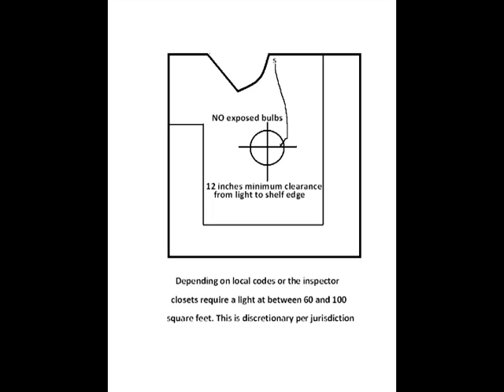Your light source can be no closer than 12 inches from the light to the shelf edge. This prevents burning if the light bulb should fail and come in contact with anything you have stocked on the shelving there.